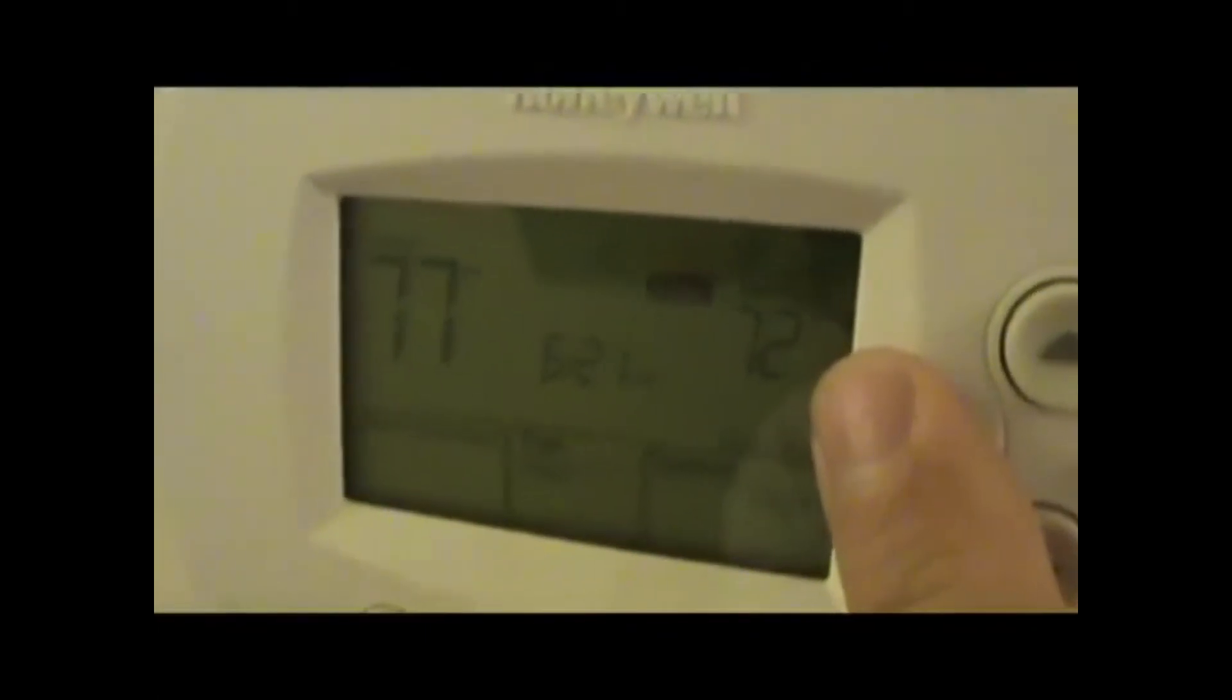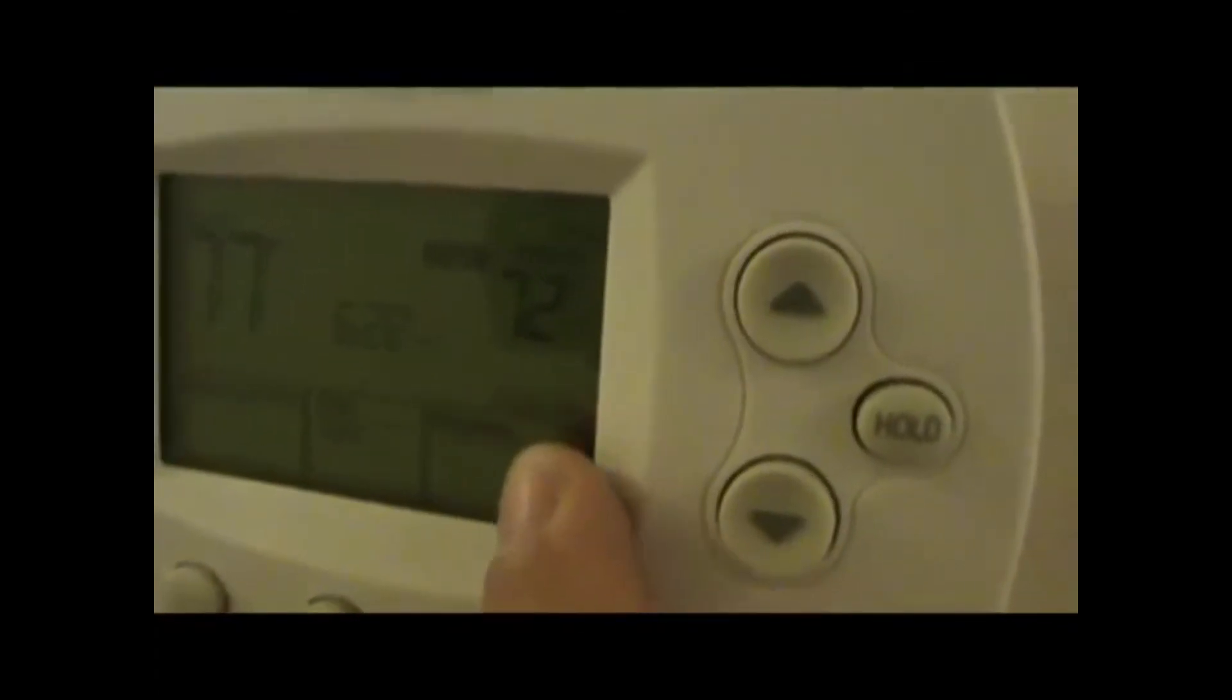Well, I can see the fans blowing, so I know the fan is working, and that's the inside fan to the air handling unit, but I put my hand over the register and it does not feel cool. Well, you need to check the obvious. You need to make sure that it's set on cool, that your temperature setting is lower than the temperature indicated, and the greater the difference between the two numbers, the bigger the clue that something is amiss. So I have my fan on auto and the setting on cool says cool on. So make sure that it's demanding cooling, especially if you have kids. You know, someone could have messed with it. You never know.